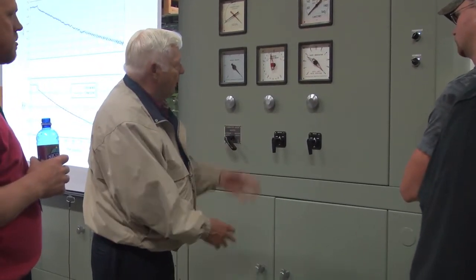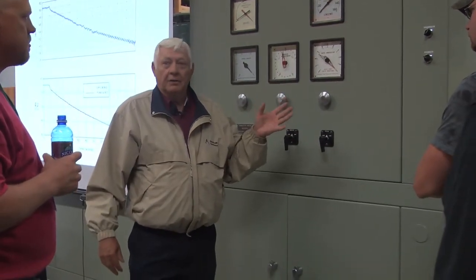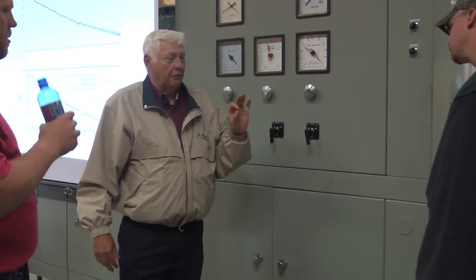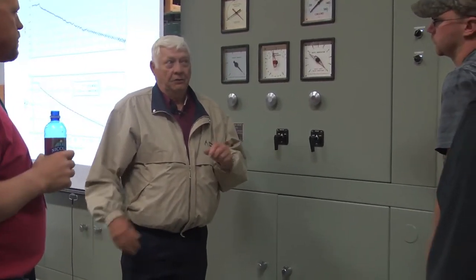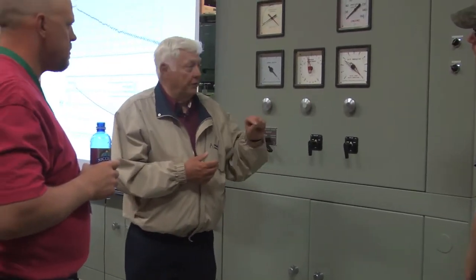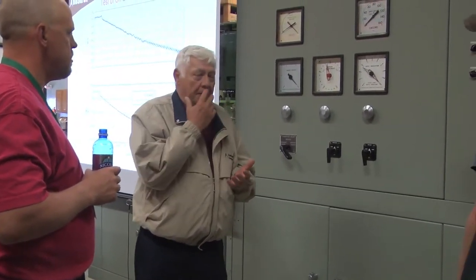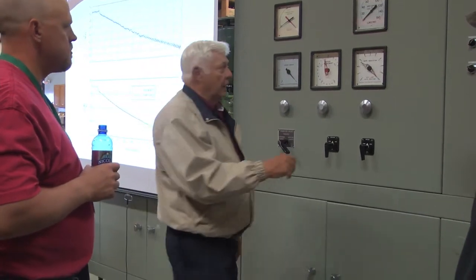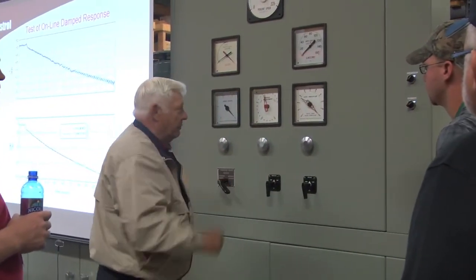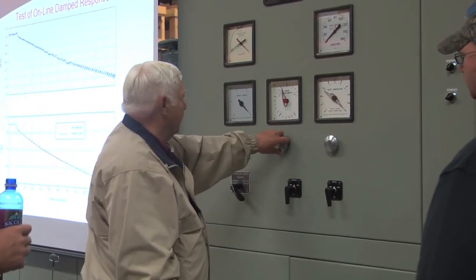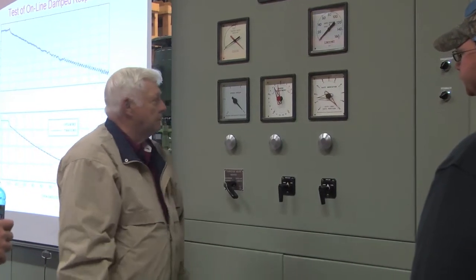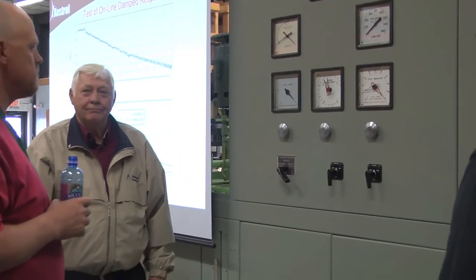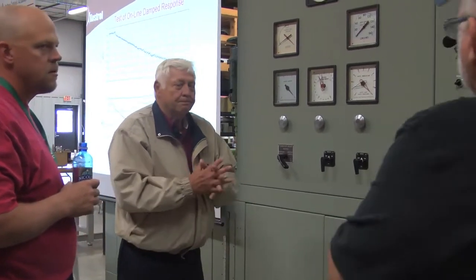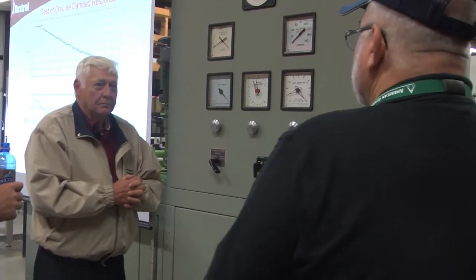Everybody see what I was talking about? The thing I wanted to show you is that you can calculate all that stuff, so then we know if the unit's working the way it should. We know this unit's working the way it should because it came out pretty close to our calculation. Now, we don't know how much that other needle's open, but you can play with that when you do the other part. I'm going to go back to the dash pot bypass and put 1 turn in there and watch the difference in response. I think we're going to find that other needle is way too open on this unit. But change it. Show them.